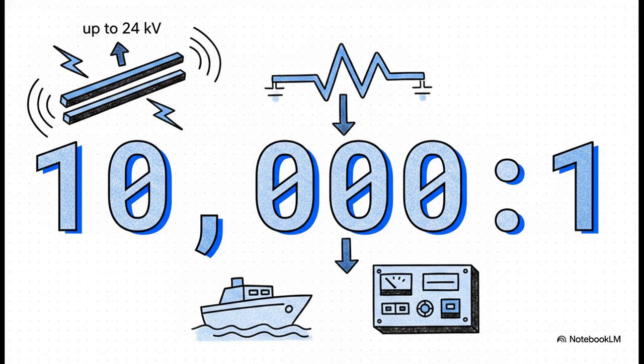So how do we fix that headache? Enter the modern alternative, the resistive divider. Its absolute secret weapon is a partition ratio of exactly 10,000 to 1. What this means in plain English is that it takes a primary voltage ranging anywhere from 0 all the way up to 24 kilovolts and perfectly, linearly scales it down to a tiny, completely safe output voltage. It's always directly proportional to the primary busbar with zero magnetic baggage.